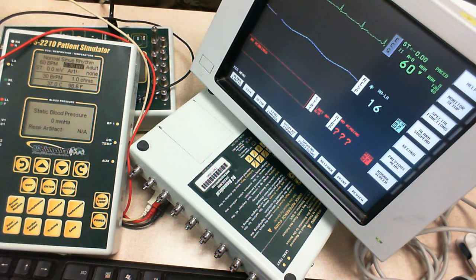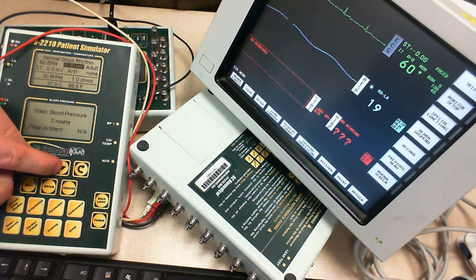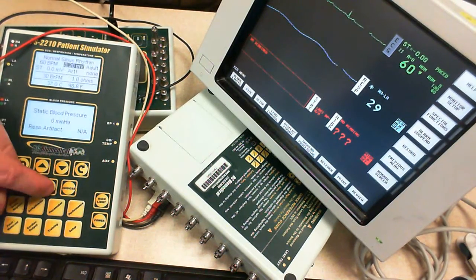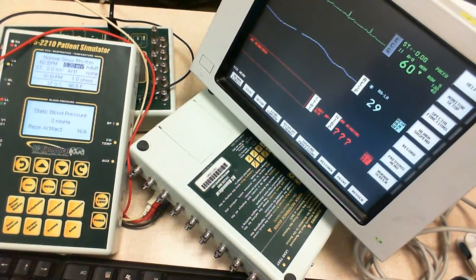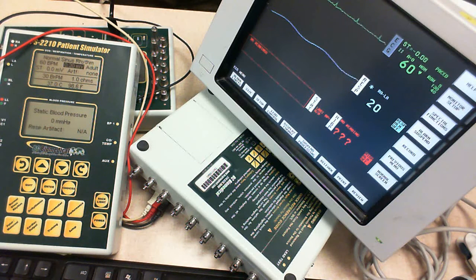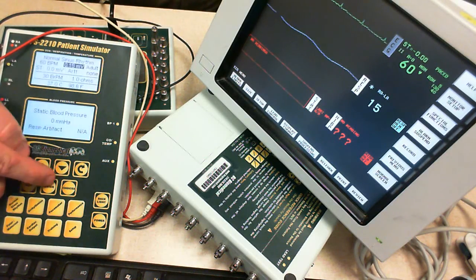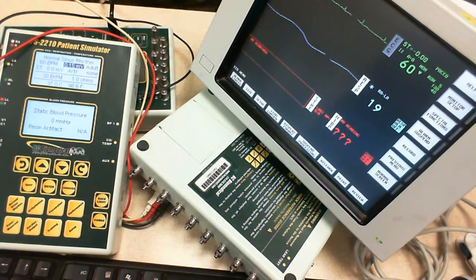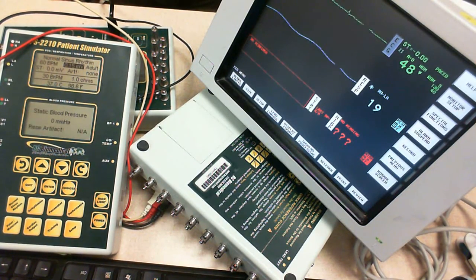I do give it about 5 seconds to adapt. Remember, there is a slight delay in things. I'm going to go ahead and go down to 20. Let's see what happens. Most monitors have that 60 beat per minute drop off right about now. What I'm going to do is I'm going to go down to 15 and we'll see how this thing does. Ah, notice a failure. There we go.